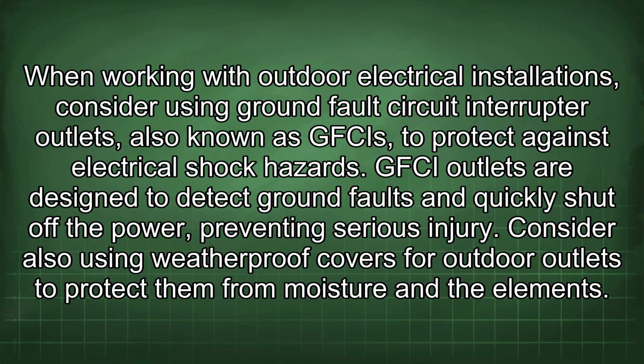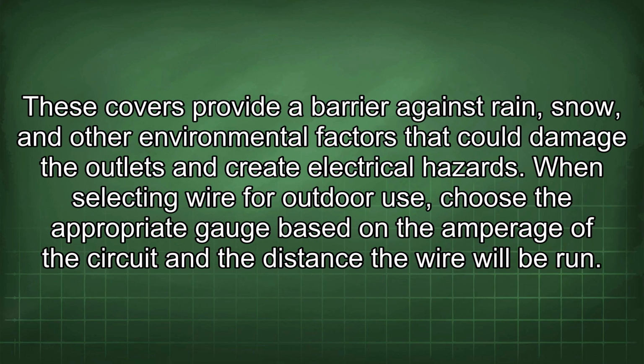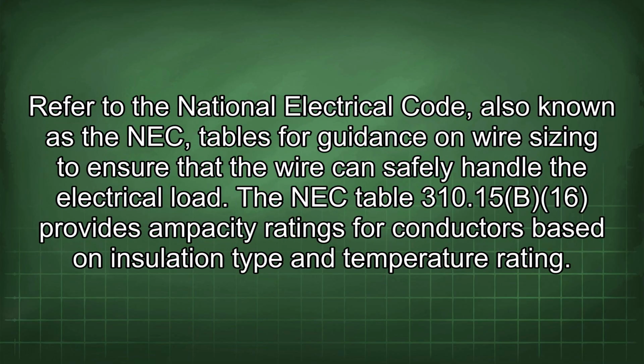Consider also using weatherproof covers for outdoor outlets to protect them from moisture and the elements. These covers provide a barrier against rain, snow, and other environmental factors that could damage outlets and create electrical hazards. When selecting wire for outdoor use, choose the appropriate gauge based on the amperage of the circuit and the distance the wire will be run. Refer to the National Electrical Code, also known as the NEC, tables for guidance on wire sizing to ensure that the wire can safely handle the electrical load.